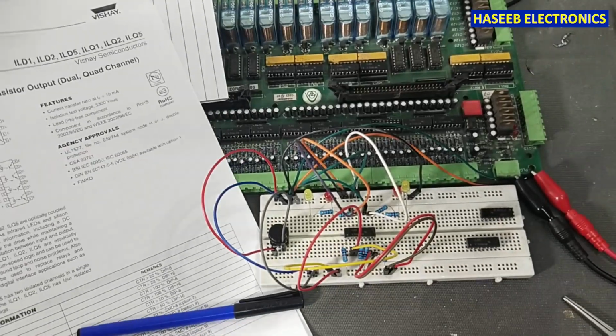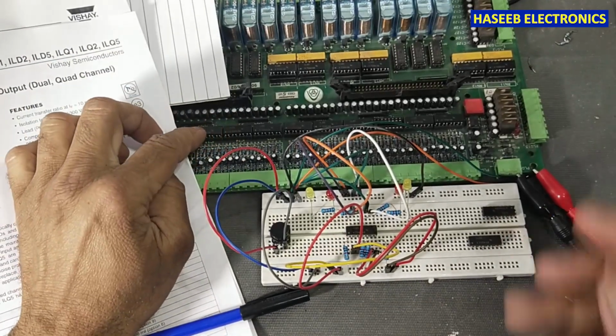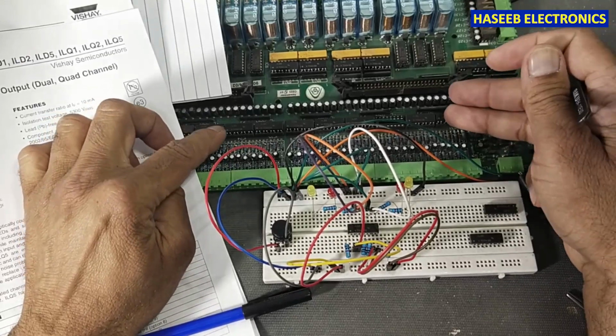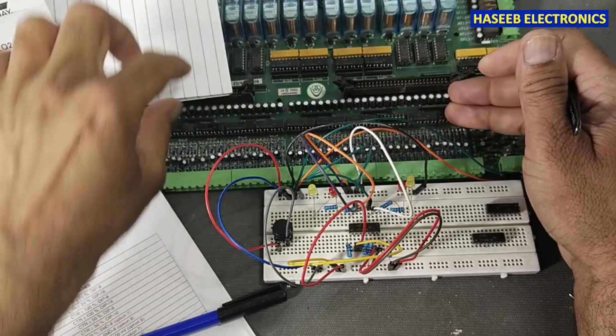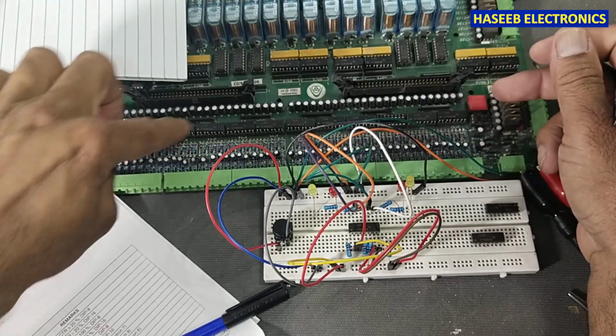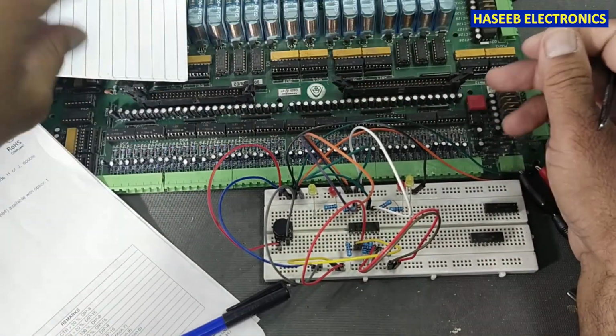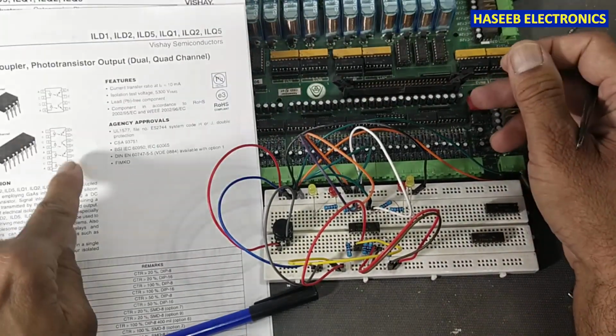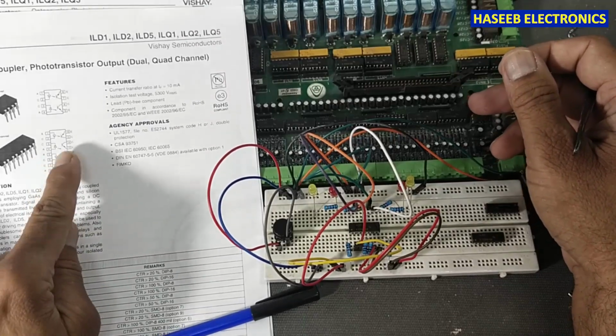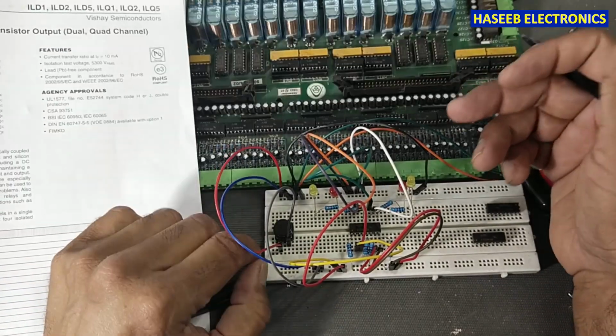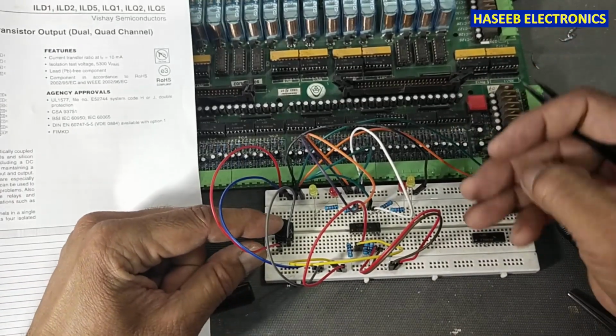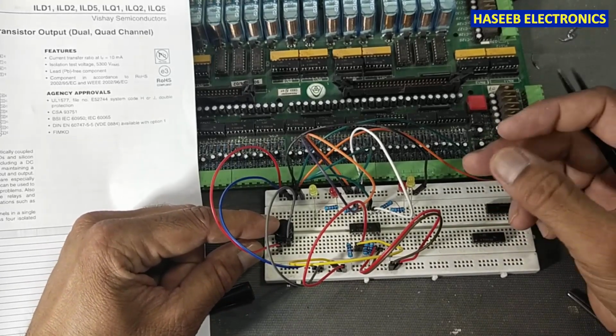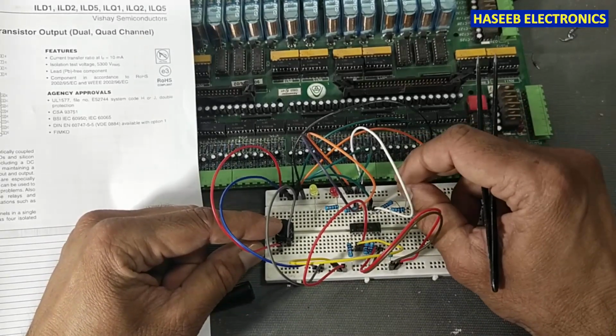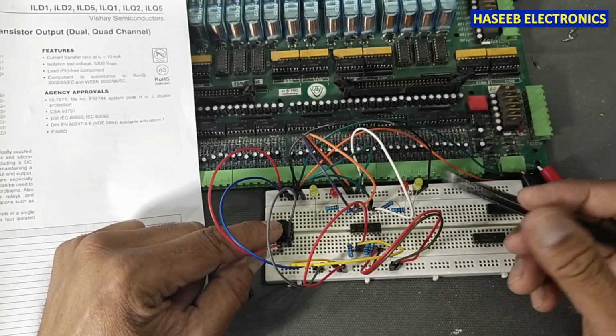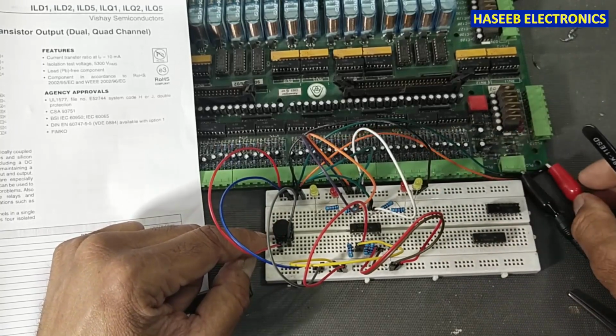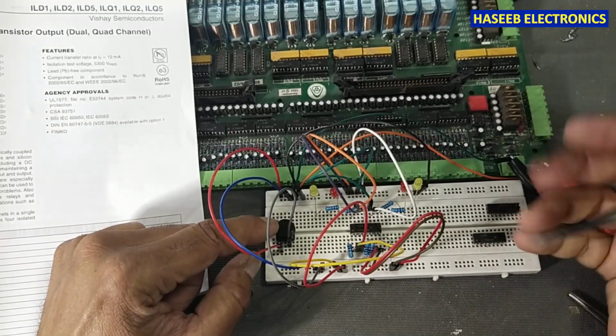Today I have this voltage interfacing board and it is using a huge number of optocouplers. We can see this complete line, and here is how we can test an optocoupler. It is a 4-channel optocoupler, ILQ5. To test it in an easy way, you can make this simple tester and you can test in the field. Just apply 12 volts, that is a common power supply.